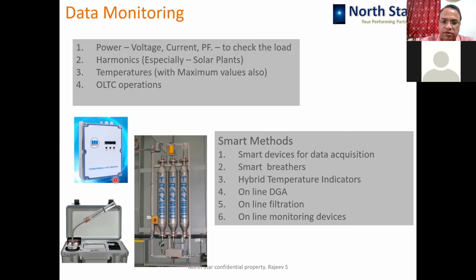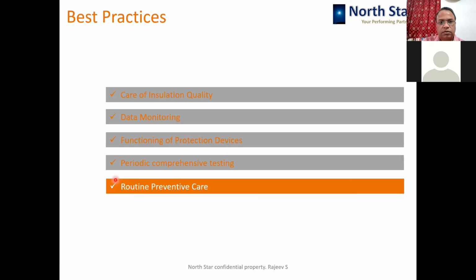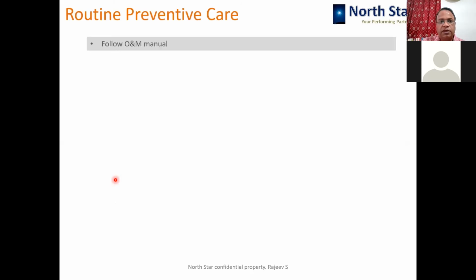Many times we get from our customers that every year we do a lot of testing, we get a lot of reports, but we are not able to use the data that is coming to us. So that was the case till very recently, where many organizations follow the maintenance and testing guidelines and frequencies and schedule regularly, but all those reports just go into the files and that data is not put into use. So the time has come that the data has to be used for the longevity of the system and uninterrupted service of the transformers. Now, routine preventive care, if we see here, few points about the maintenance of the transformer.